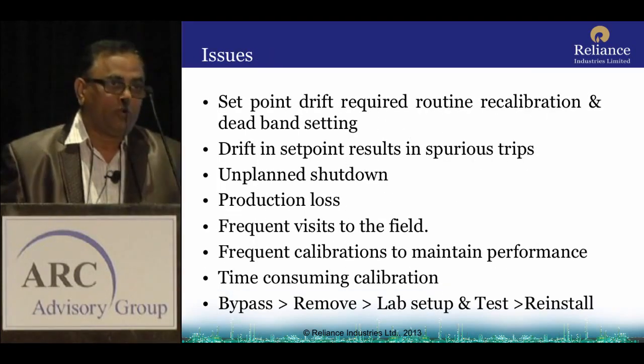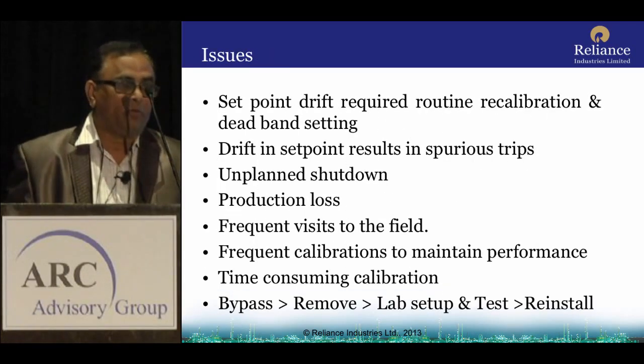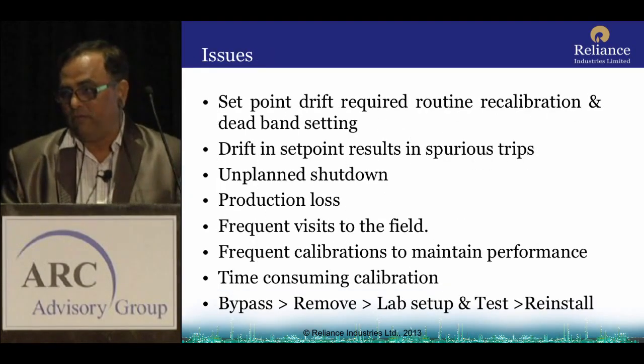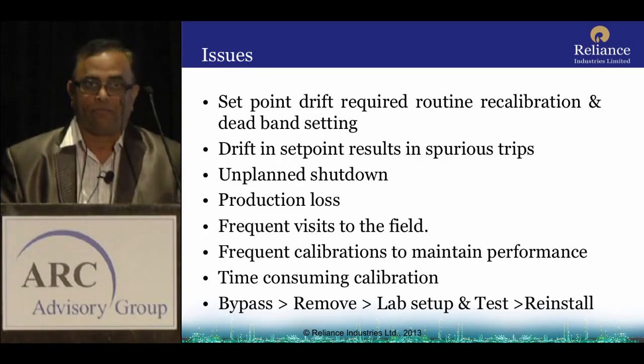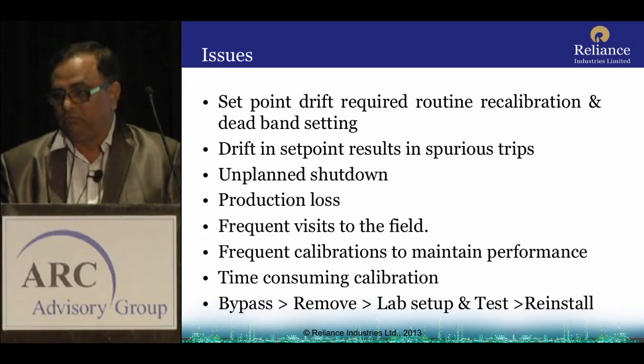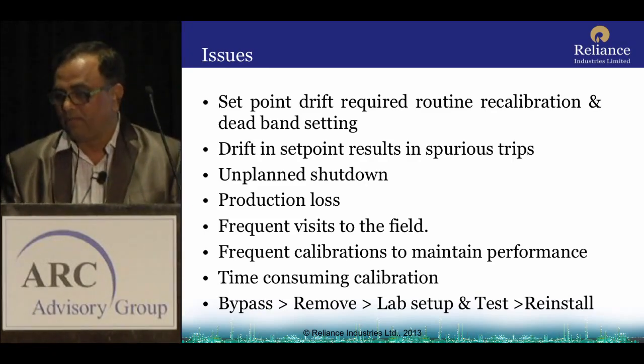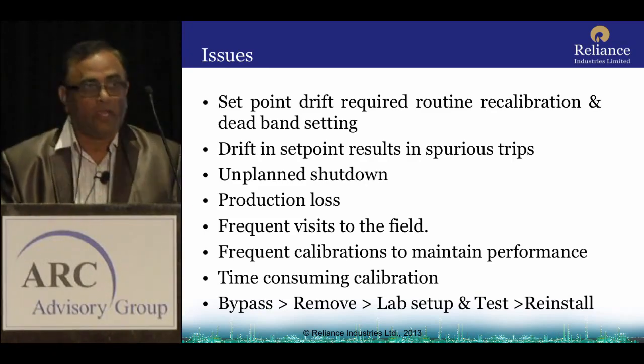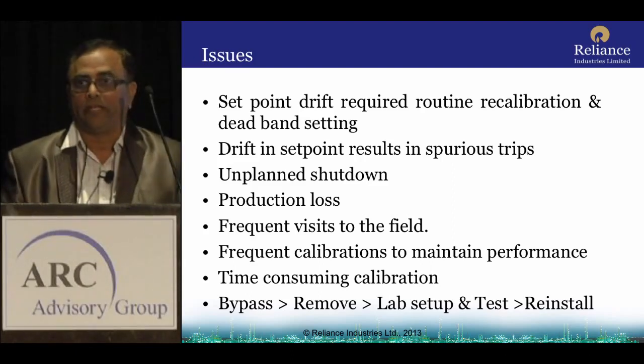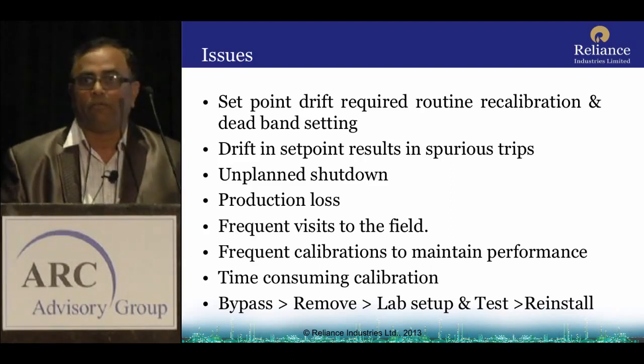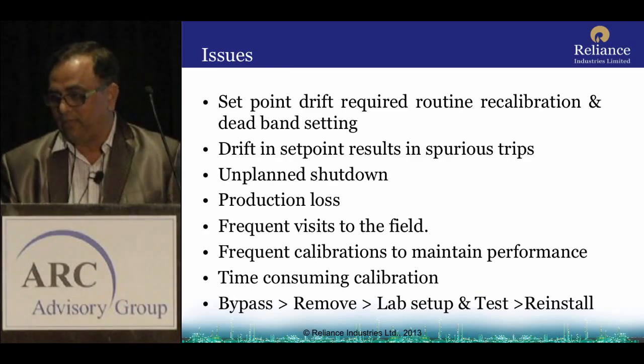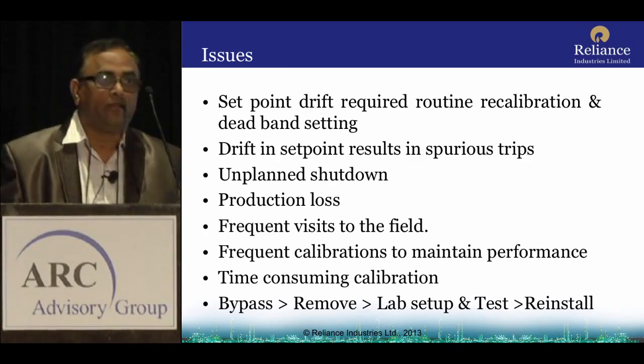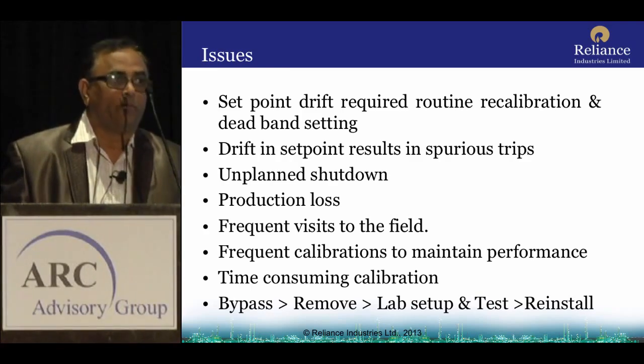Drift in set points because of external vibrations or other things will lead to a spurious trip and plant shutdown, resulting in production loss. Again, the technician or the engineer has to rush to the plant. It's an unnecessary, unwanted visit to the plant.